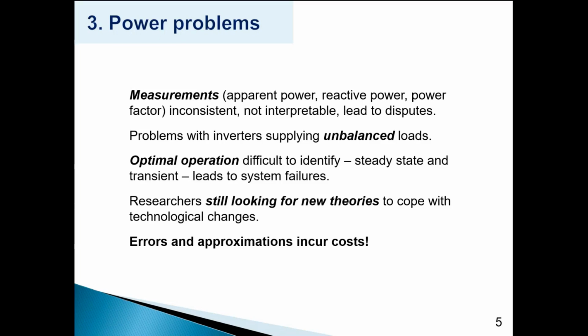We have problems with inverters supplying unbalanced loads. We have a problem identifying optimal operation, both in steady state and transient. And that leads to system failures. And I'm not talking about load shedding. I'm talking about systems going down because they're unstable, they lose synchronism, things like that. And behind all of this, we see, if we're familiar with the literature, many, many researchers still looking for new theories to cope with all the technological challenges that are coming up. Because errors and approximations in control and analysis and in metering incur costs for somebody, either the supplier or the customer, or sometimes for both.